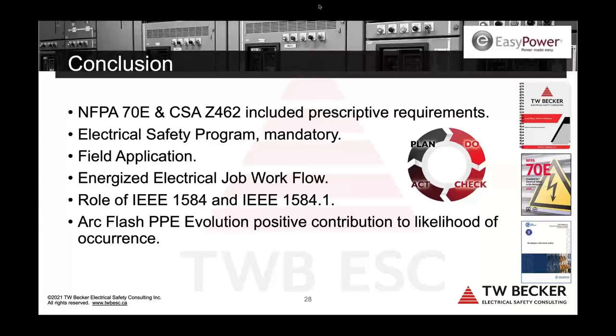1584.1 tells you how to methodically do this very specific power system study, short circuit analysis, protection and coordination, then incident energy analysis. And there's more to it than that, parameter selection. And 1584 says, here's what you might want to put in your report. So you can do QA/QC on your study and on your report. So 1584.1, look it up if you don't have a copy, buy it online. It's actually cheaper than 1584 itself, all right?